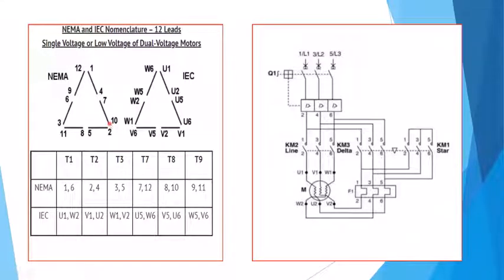The benefit to that was, again, it would drop the inrush current, cut it back, typically in half at least. And that's what this contactor over here is for, that does the Y, or the star they call it. And then after it gets running, it's got it across in the delta. So KM2 and KM3 will pull in, and that'll end up giving the motor back again full 480 to that winding. So all we were doing is basically just reducing voltage.